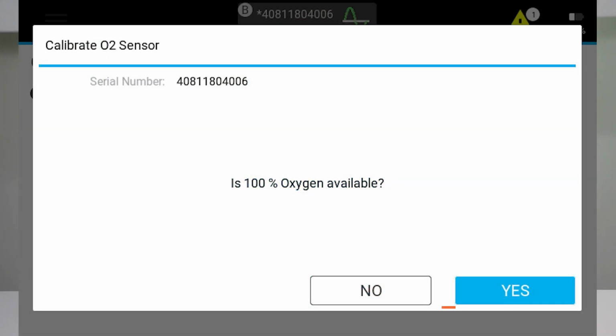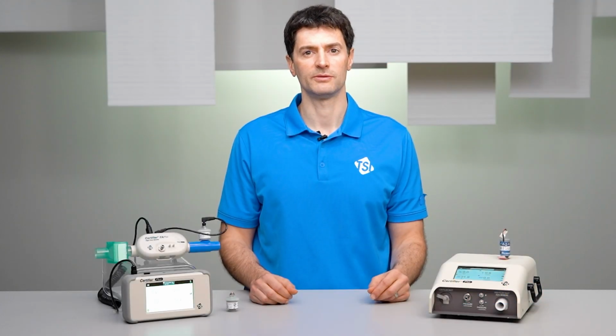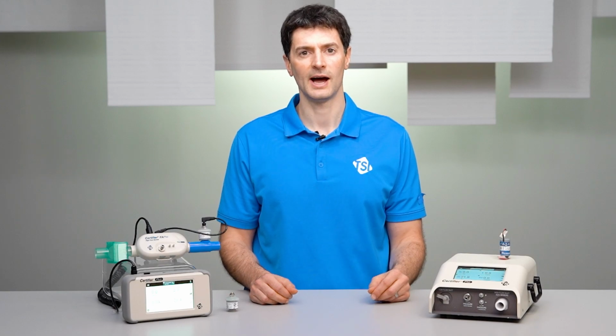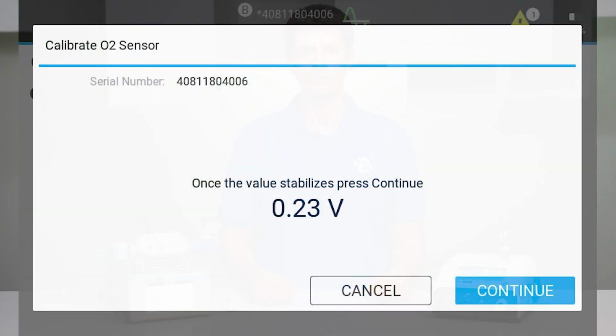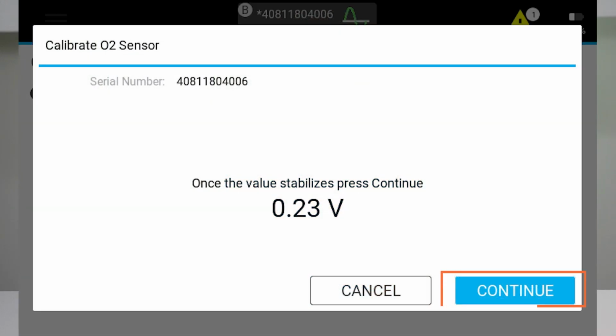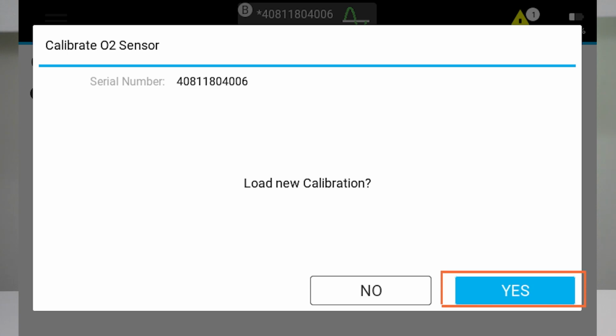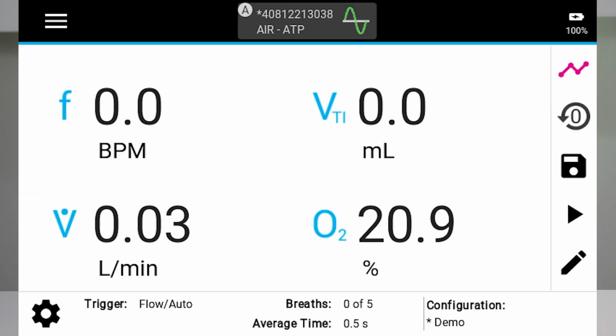If you have 100% oxygen available, then proceed with this next step. It's recommended to use a flow rate of 4 to 9 liters per minute for the oxygen gas calibration. Again, once the voltage values displayed on the screen are stable, press Continue. Once complete, press Yes to load the new calibration. You are now ready to make oxygen concentration measurements.